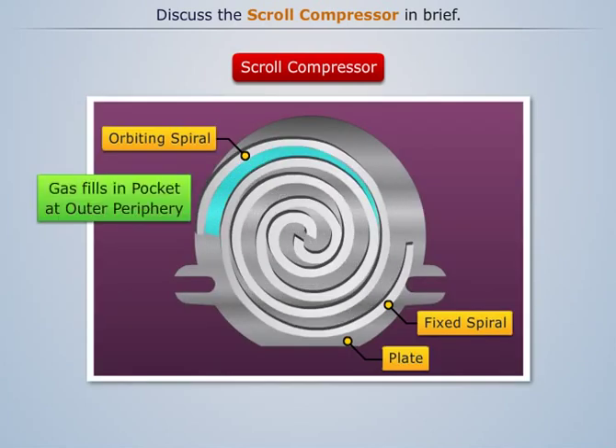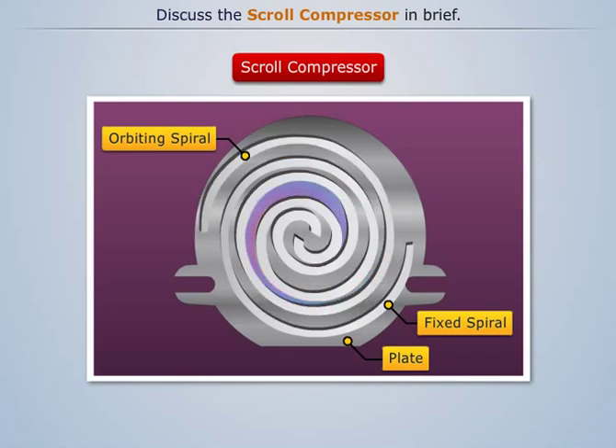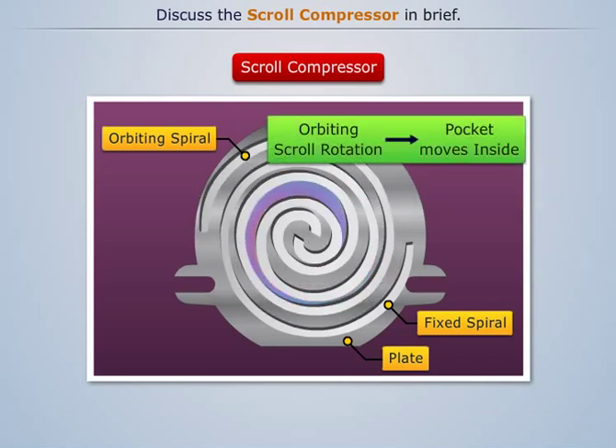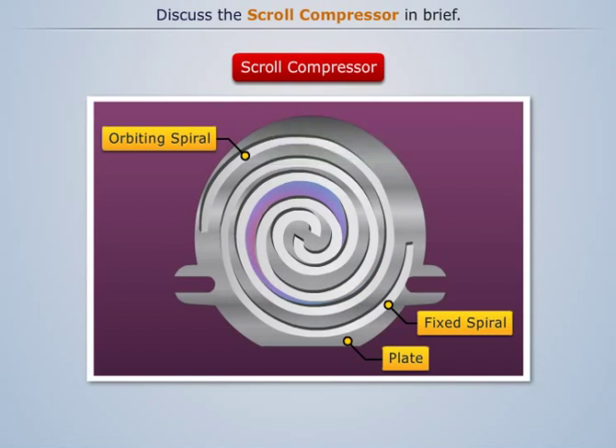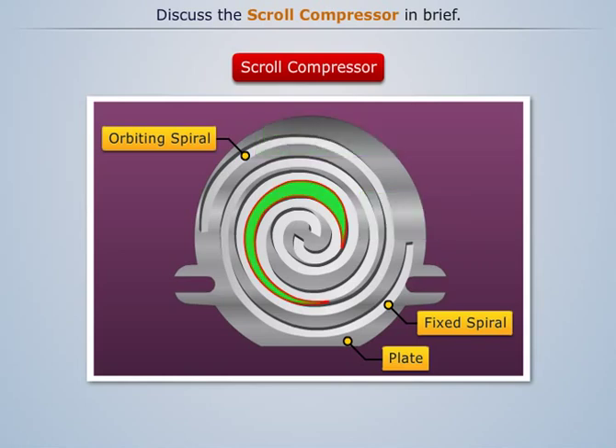The movement of the orbiting scroll causes gas to be filled in the gas pocket of a given volume at the outer periphery of the scrolls. Due to continuing movement, this gas pocket gets sealed and cut off from the atmosphere. Further rotation of the orbiting scroll causes the gas pocket to move inward from the outer periphery, resulting in a continuous reduction in size of the gas pocket.